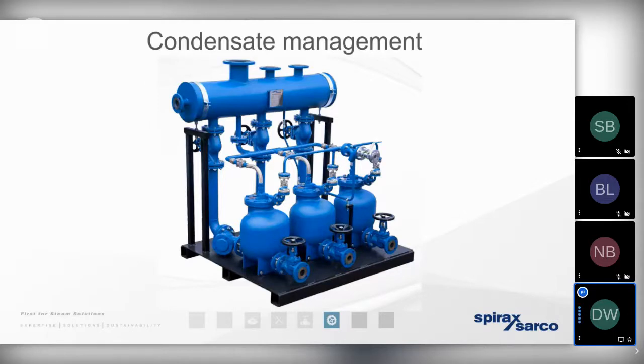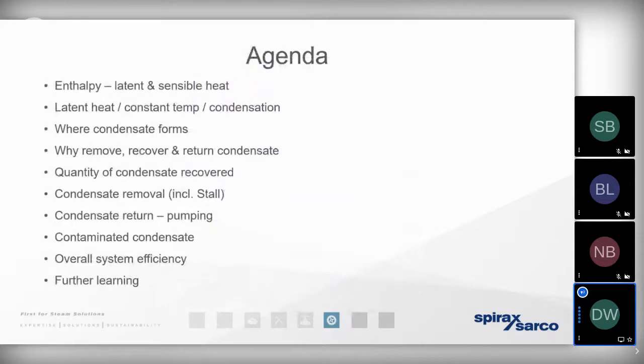And as we go through the presentation today, it'll probably become clear why it's the condensate side of the loop, the wet side, that so often causes problems for so many mechanical engineers, especially those who may be more experienced with liquid-based systems, such as low temperature hot water. So today we're going to go through the presentation to fully understand what condensate actually is and how we need to treat it completely differently to water, and to help us to both understand the problems it can bring to a process by not draining the condensate away, and also the benefits it can bring if we can find a way to reuse the heat energy present within that condensate.